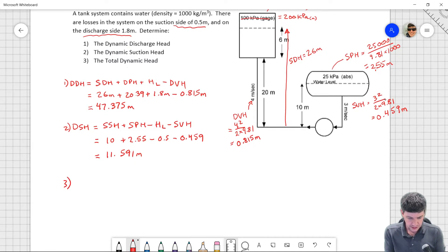The total dynamic head is going to be equal to my dynamic discharge head minus my dynamic suction head. And it's going to be equal to 47.375 minus 11.591, 35.78 meters.